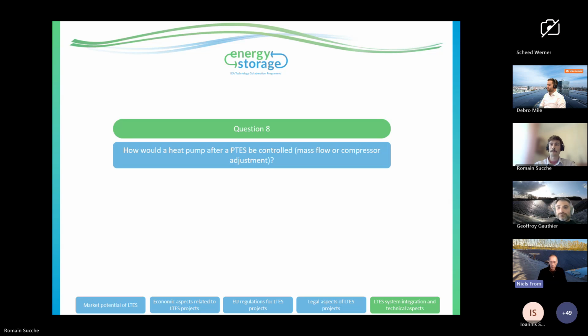You should be aware that if the water flow is controlled by another factor, for instance the heat demand, then the heat pump cannot control the mass flow through it, and then it could be difficult to maintain a very fixed outlet temperature from the heat pump.